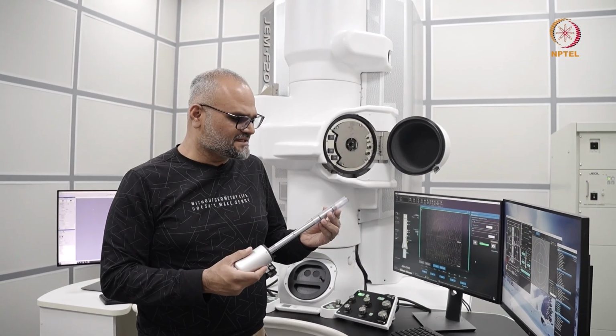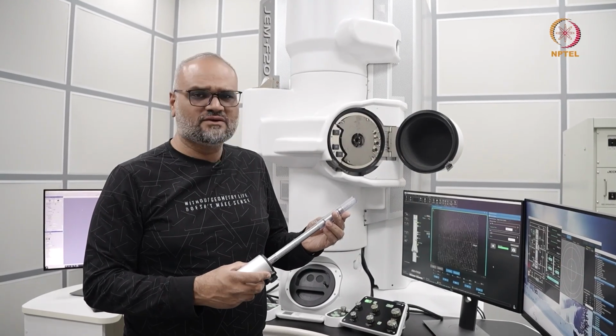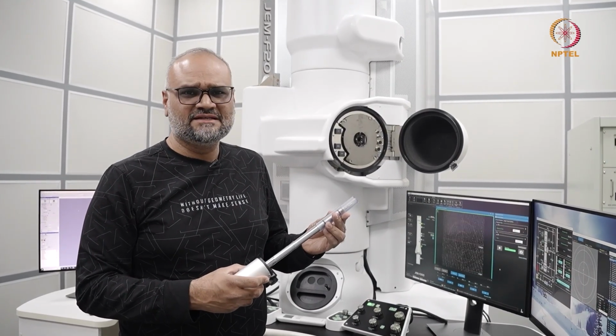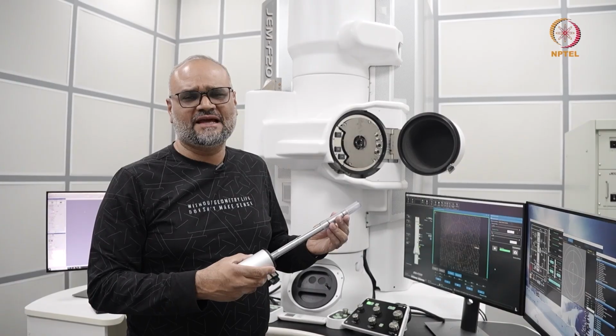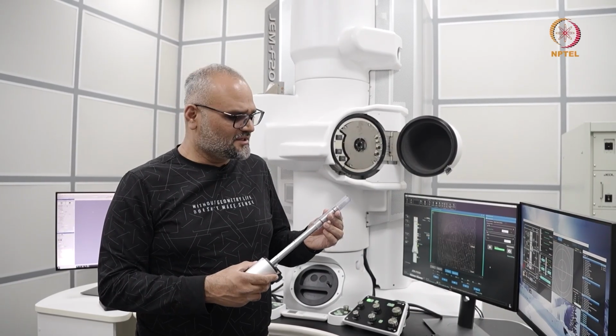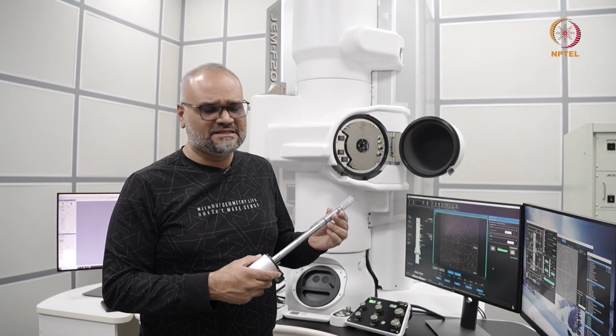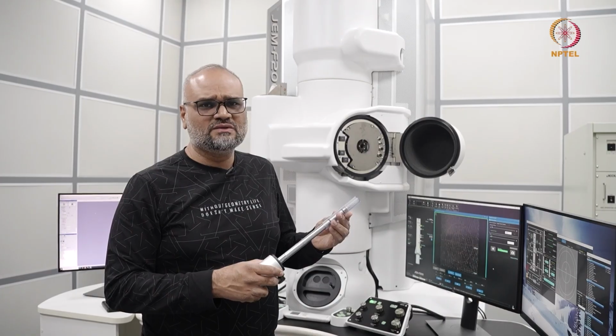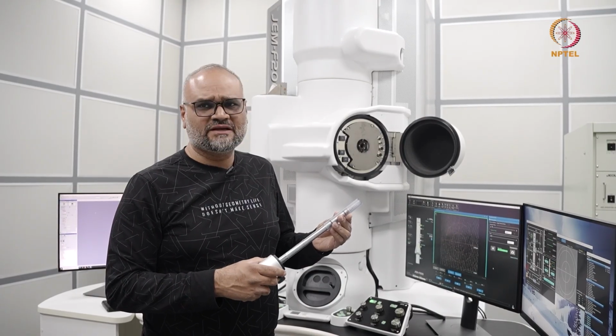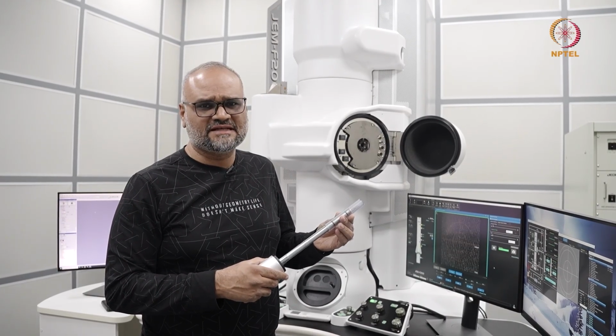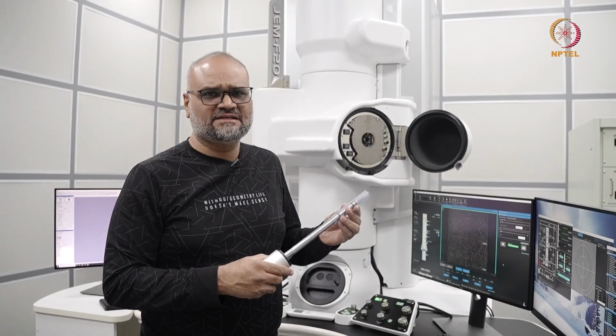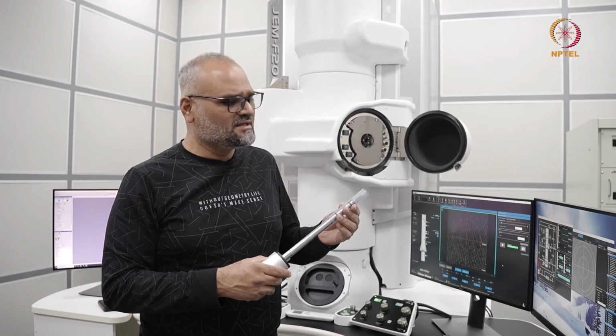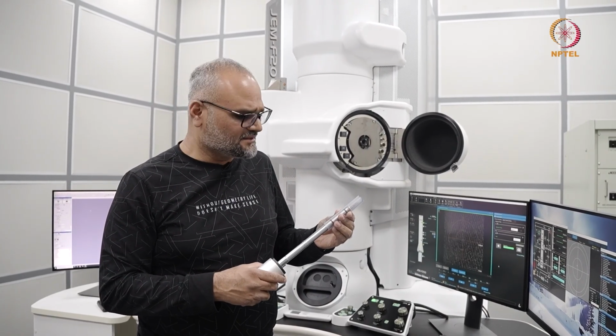So here we have the single tilt holder, and we've loaded a gold cross grating sample in this. It's a standard sample which you use for calibration of the microscope. One of the reasons why I want to put this in is just to show you some of the possibilities on this microscope to do high resolution TEM and STEM. And for diffraction and tilting, I'll show the same on another aluminum sample a little later.